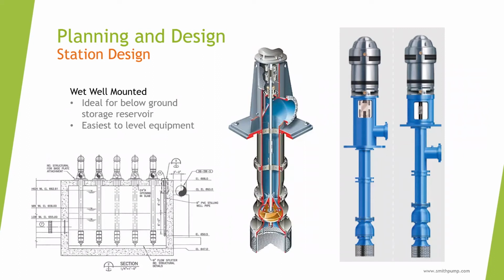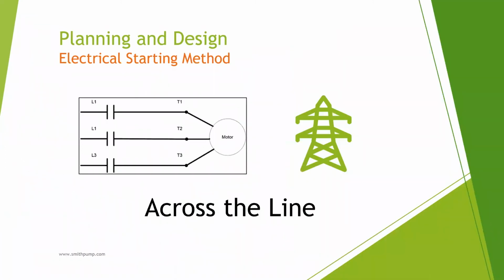Wet pits are great if you want to combine your storage tank with your pumps. Prepping a firm level surface for setting pumps is easier on a wet pit. They only need a sole plate installed and leveled, as opposed to leveling the entire barrel unit. We also recommend keeping concrete hole as large as possible for future upgrades for larger equipment. We have seen upgraded equipment not fit through the concrete hole before.